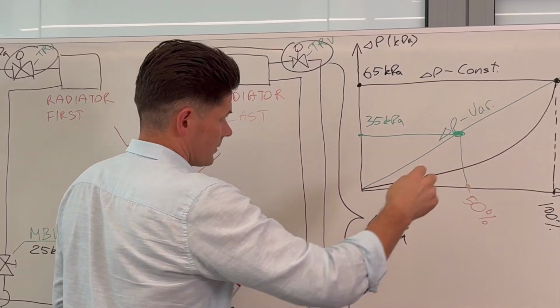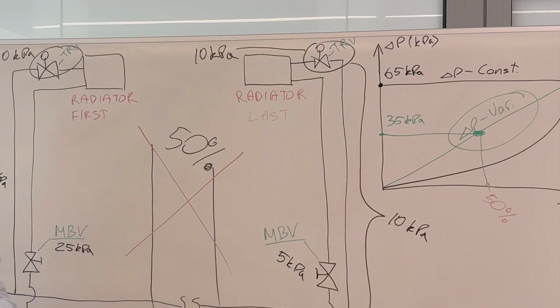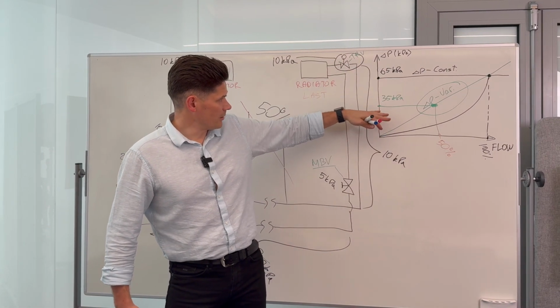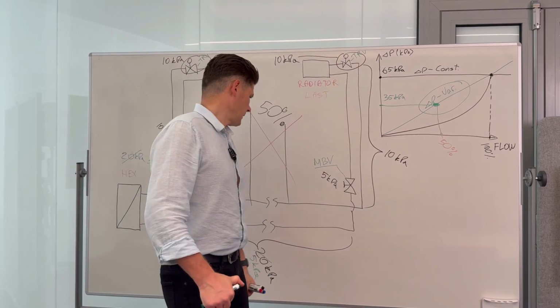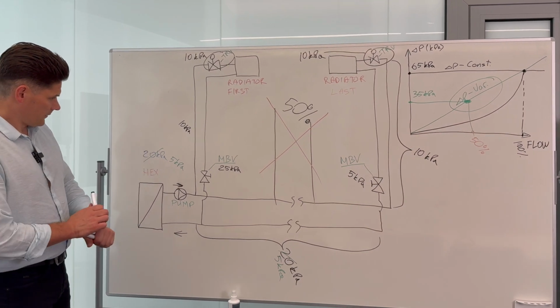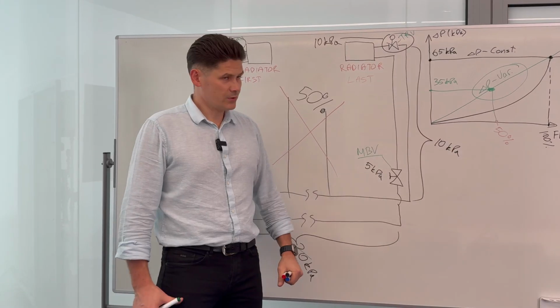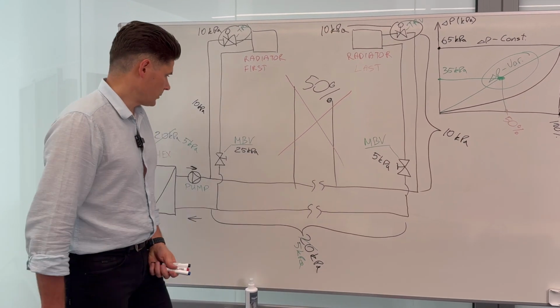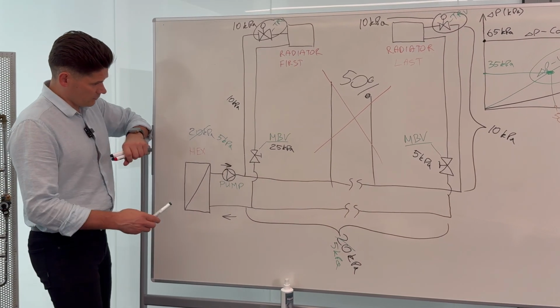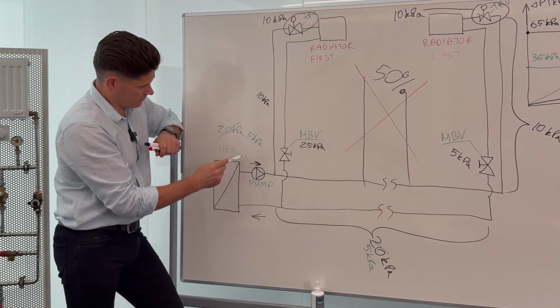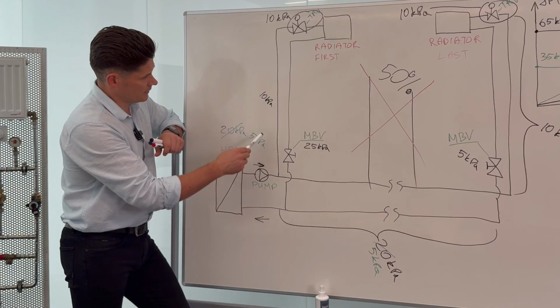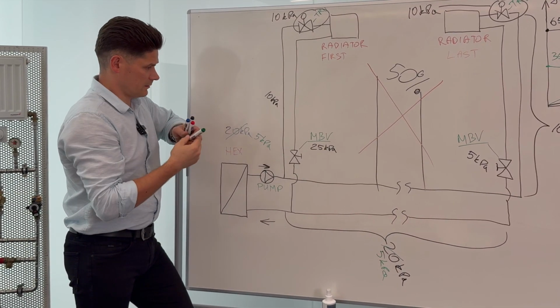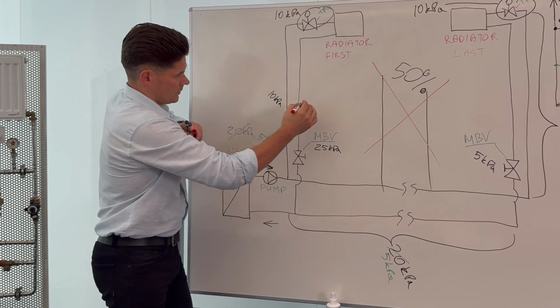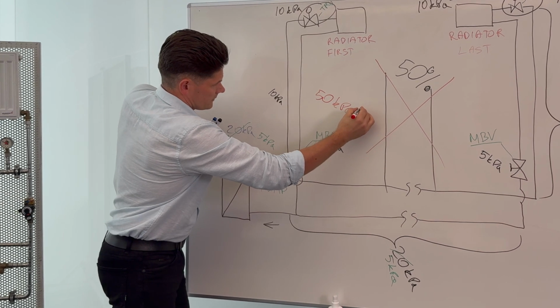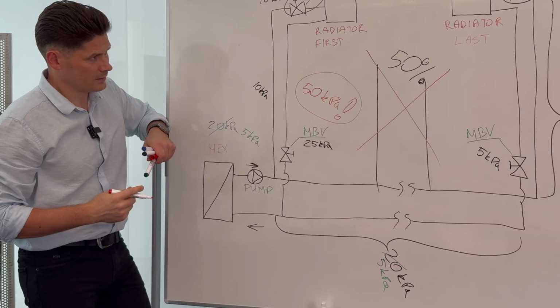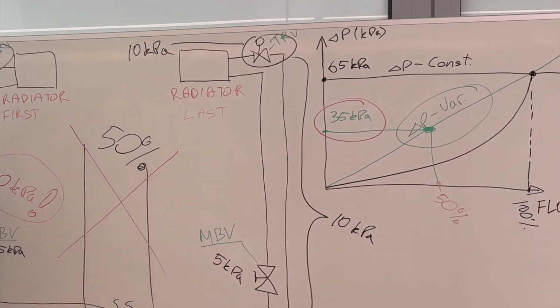Okay, so my new working point is something like this. The system is working with a variable speed drive, and now the circulation pump spins slower and produces 35 kilopascals. 35 kilopascals is enough for the riser which is the last one. But how is it with the riser which is the first one? Let's calculate how much delta P we need here. So 5 kilopascals plus 25 will be 30, plus 10 will be 40, plus 10 will be 50. So we need 50 kilopascals to have the right flow for the first riser. What we get is only 35.